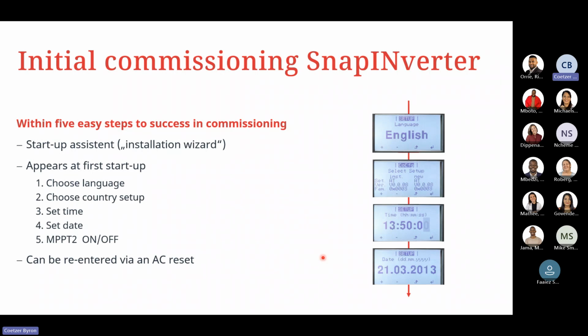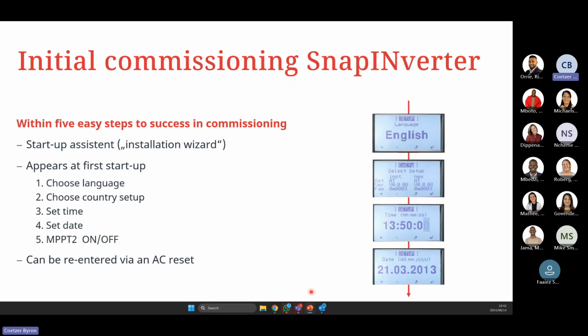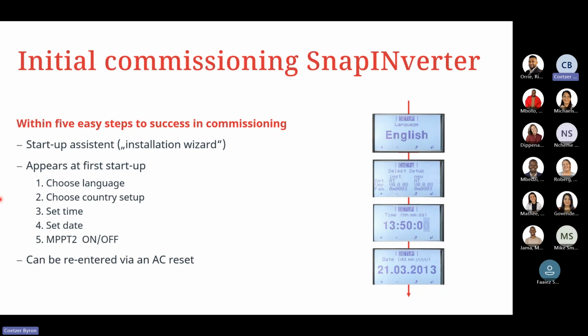So with the initial commissioning of your Snap inverters, these 4 or 5 simple steps will pop up when you are using a Snap inverter, which we like to call the installation wizard. When you are first booting up the unit, you'll have an option to select the language, the country code setup, and you'll set your date and time. Lastly, if the unit has 2 MPPTs, we can set whether MPPT 2 is on or off. This can be re-entered via the AC reset code that is available on request from Fronius.